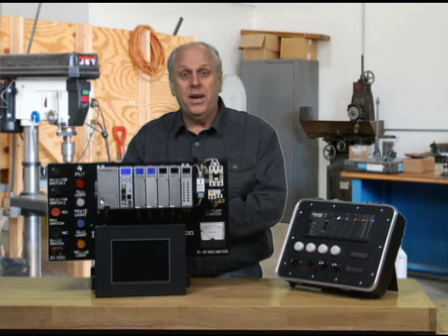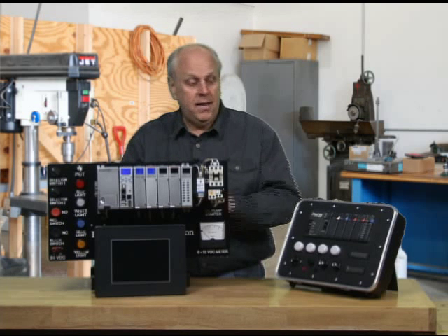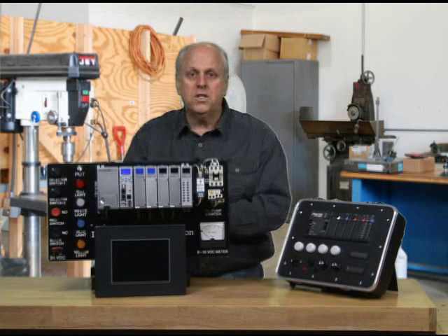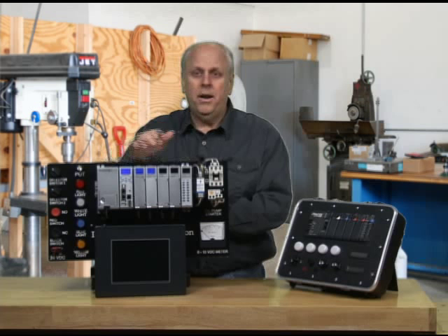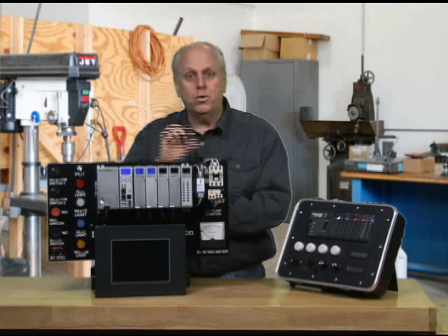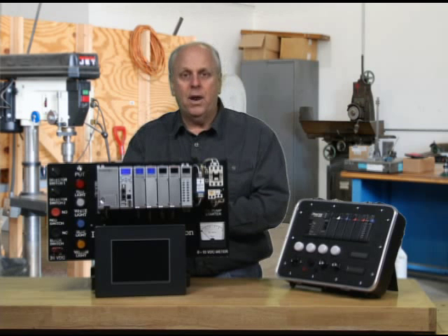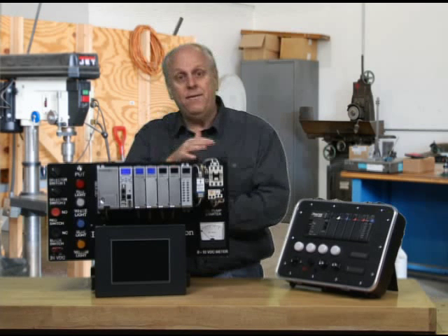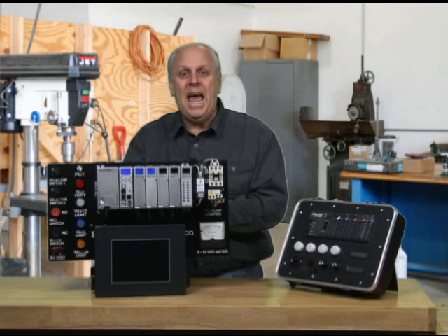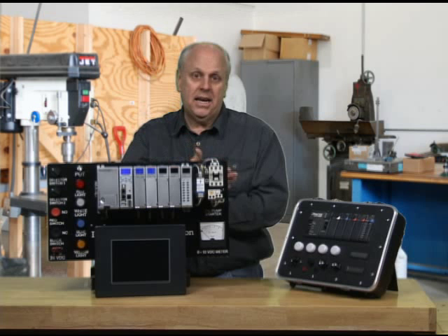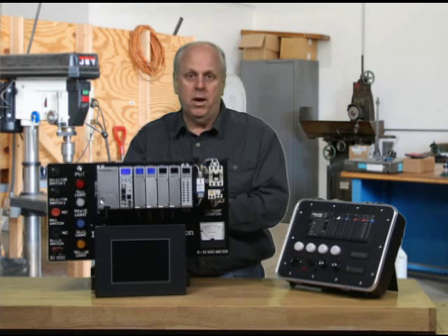Another feature it has, which is very nice, I can break them into separate tasks. In this unit, we used to have one big, massive program. I used to call it spaghetti programming. In this one, in the software, I can create regular folders, like Microsoft folders in a window, and in those folders, I put my ladder logic that I want to execute. And I can have those folders, or what we refer to as tasks, run based on time, based on minutes, based on seconds, based on events. I control when they run. I can have them run all the time, but I can break my program into separate tasks.